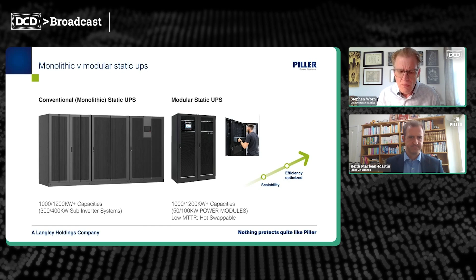So what is this operational efficiency, this efficiency optimization? Well, if we're looking at a simple 1,000 kilowatt modular static UPS with a load deployed of only 300 kilowatts, where conventional technologies would deploy all power modules operating at 30% load, we can reduce that and optimize the efficiency and deploy only 3 of those power modules to meet the low demand now. This has the effect of optimizing that efficiency, and it can easily be tailored ultimately to achieve N+1 or perhaps N+2 redundancies just at the UPS level to protect and deliver robust responses to those load changes.